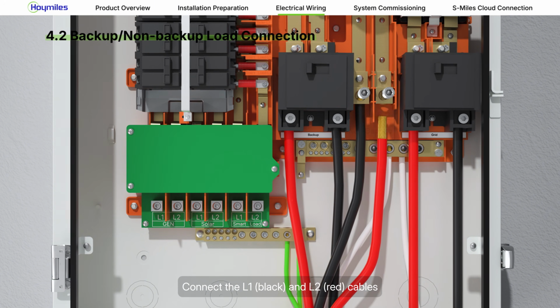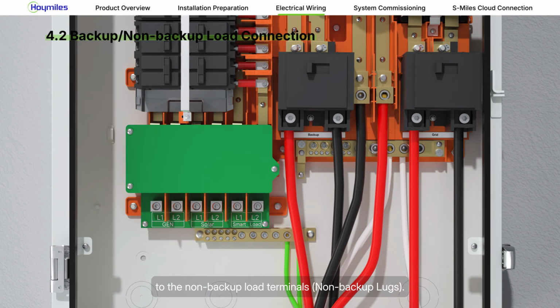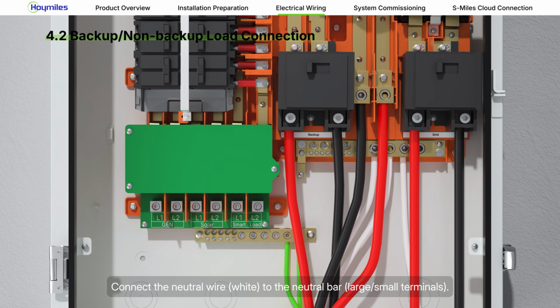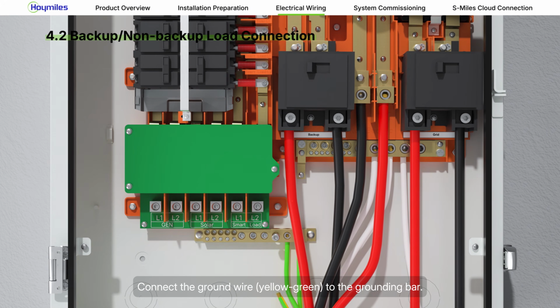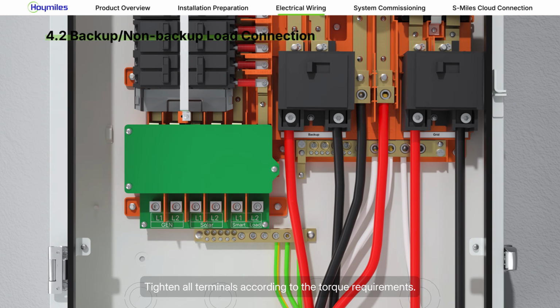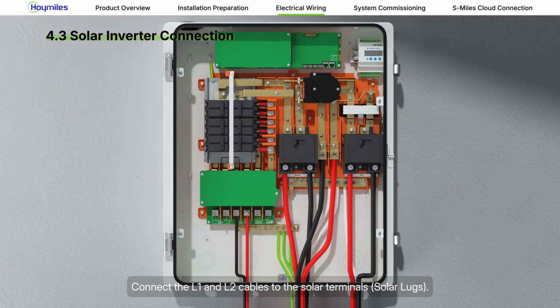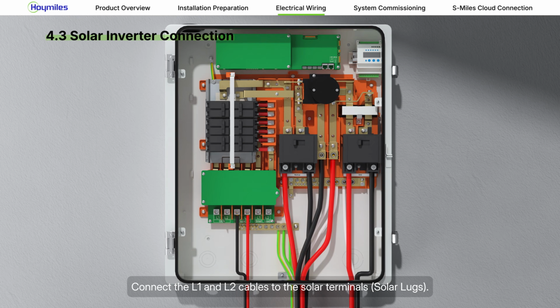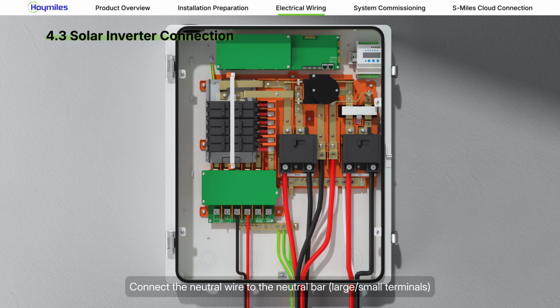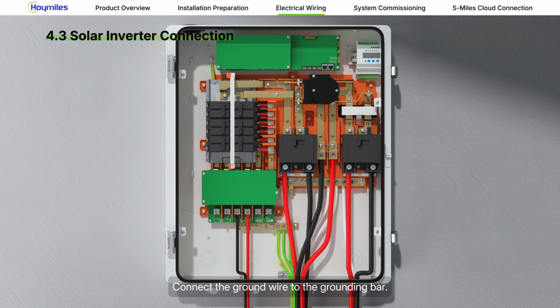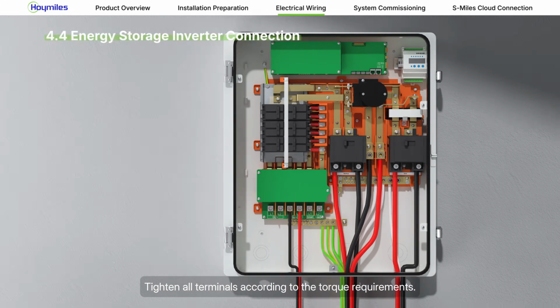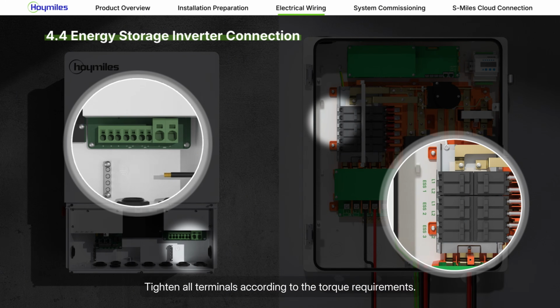Connect the L1 and L2 cables to the non-backup load terminals. Connect the neutral wire to the neutral bar. Connect the ground wire to the grounding bar. Tighten all terminals according to the torque requirements. Connect the L1 and L2 cables to the generator terminals. Connect the neutral wire to the neutral bar. Connect the ground wire to the grounding bar. Tighten all terminals according to the torque requirements.